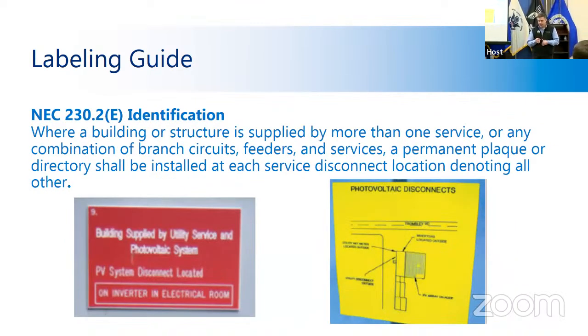All right, so for a supply side connection, like I said in the last slide, we're going to drive this home. You want to have a label, preferably a plaque or something very permanent, at each disconnect. Like on the previous slide, you can have a label where it is, or you can have kind of a map showing, here's this disconnect, the other one is right around the corner, right? So it's important for people working on your house to know where the disconnects are so they can easily create an electrically safe work condition and not put themselves in danger.